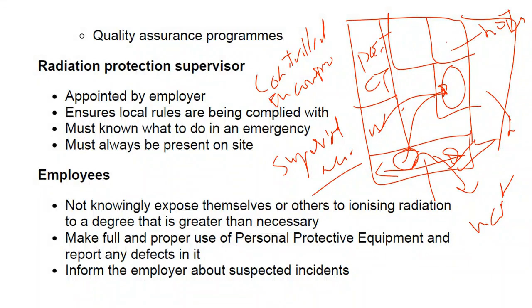The risk assessment, as I was mentioning earlier, is about explaining what a risk assessment is and what it entails. For any radiation facility, for example, if you want to acquire a CT or an X-ray or establish a nuclear medicine department, before doing anything and even before starting construction, you must submit a file to the national organization.